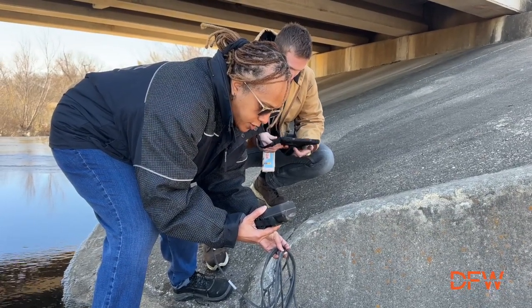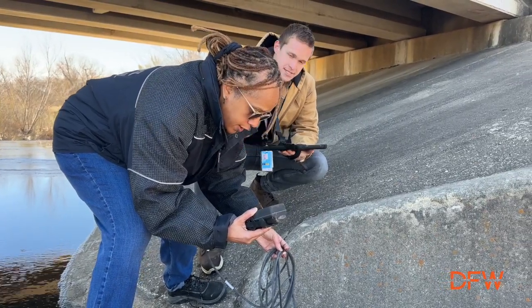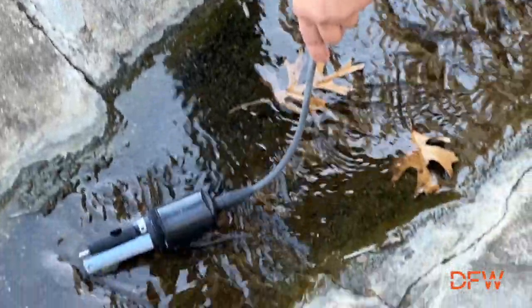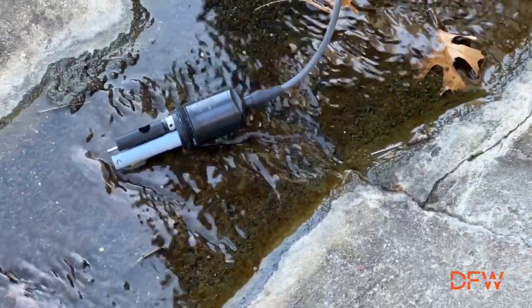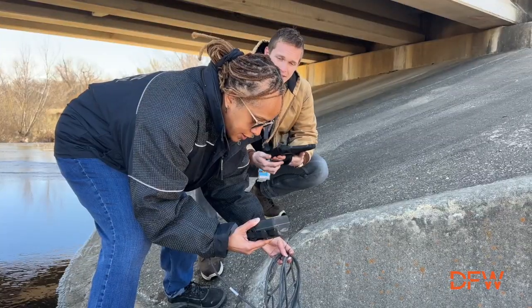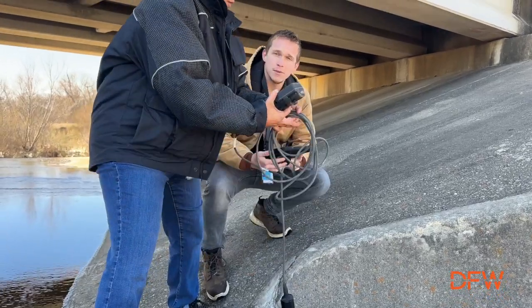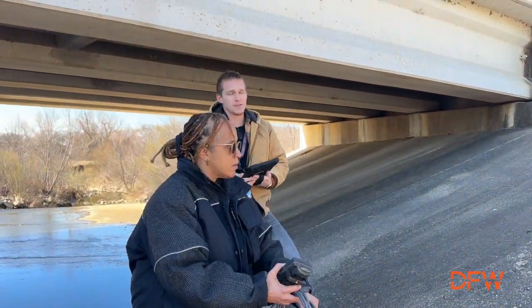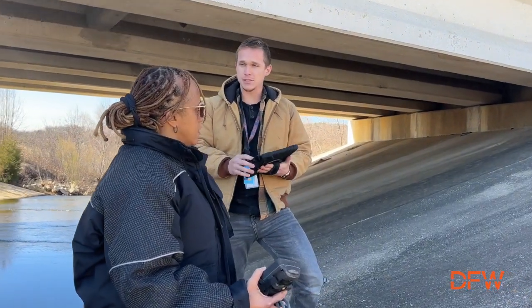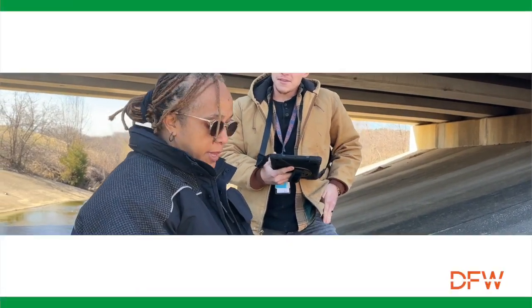You know, the pH is reading at 7.5. Is that okay with you? Perfect. We want it between 6 and 9, so that should be perfect. And DO is 10. It's great. Awesome. And even some of the other parameters, I don't see anything that really spikes out as abnormal. Okay, great. Well, maybe we check with Brandon and have him go upstream to the facility where this originates, just to make sure that nothing's happening up there. Sounds like a plan.